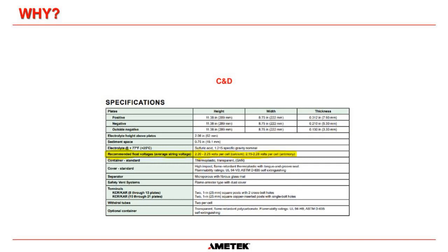Obviously, if you fill your batteries to the high level line and then you take a specific gravity reading, then your specific gravity is going to be slightly lower than if you take it when the level is at the lower line, because the distilled water that you put in the cell does dilute the specific gravity to a point. But I have never heard of specific gravity going up as they age.